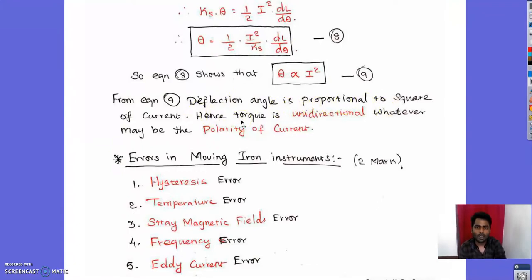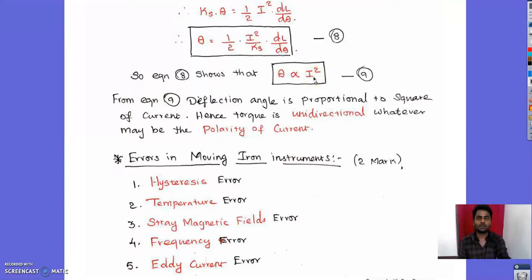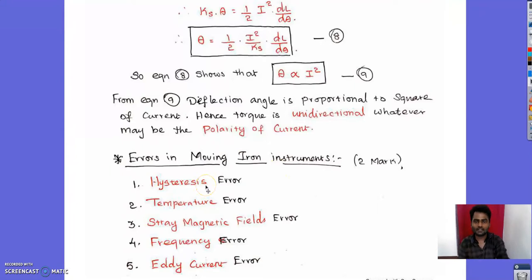The torque is unidirectional regardless of the polarity of the current, because squaring the current always gives a positive value. Therefore the deflection direction is not affected by current polarity. The errors in moving iron instruments include hysteresis error, temperature error, stray magnetic field error, frequency error, and eddy current error.